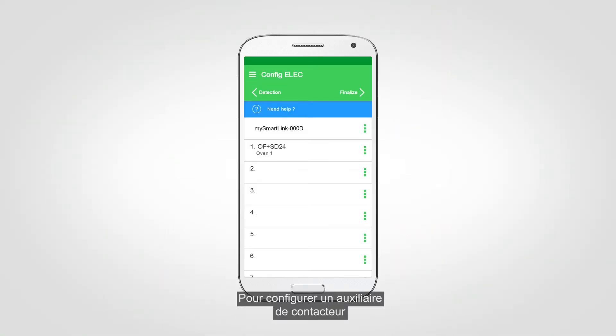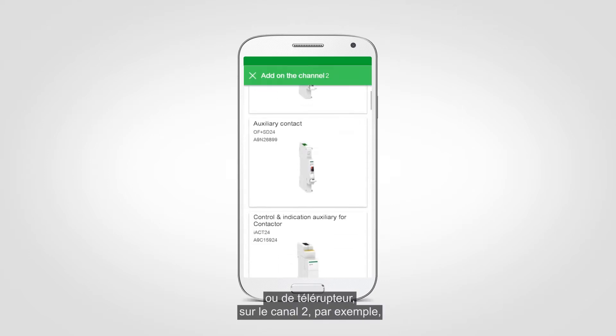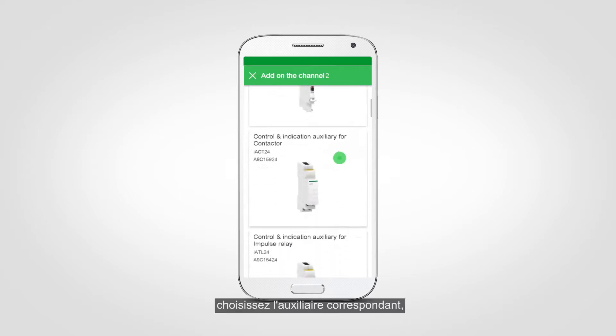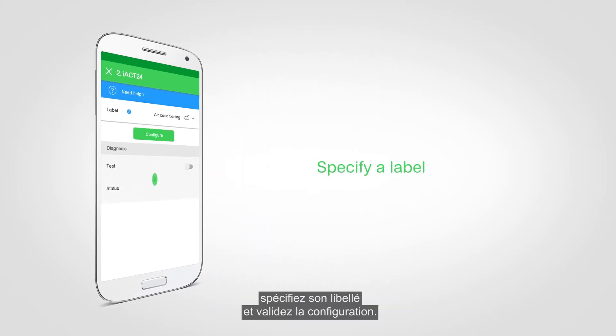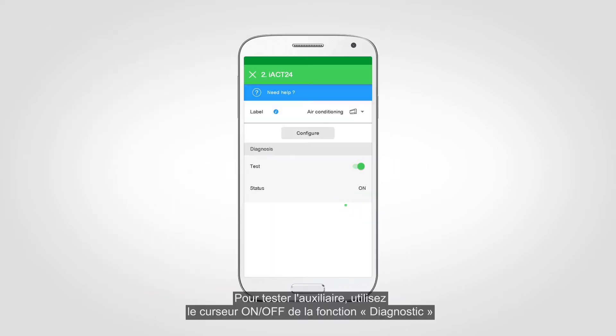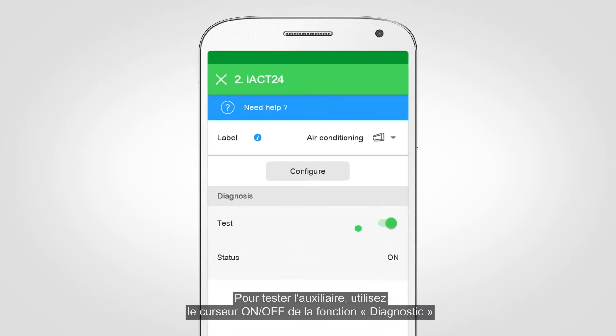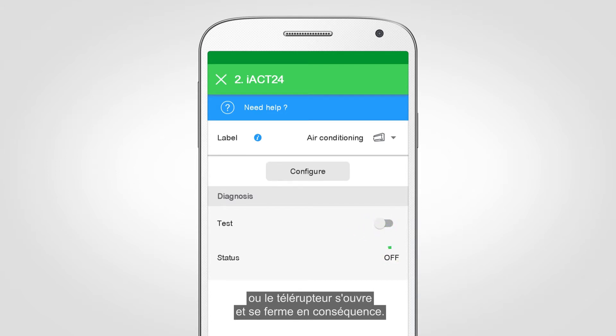To configure a control and indication auxiliary for contactor, or for impulse relay on channel 2, for example, select the corresponding auxiliary, specify its label, and validate the configuration. To test the auxiliary, use the on-off slider in the diagnosis section, and verify in the electrical panel that the contactor or impulse relay opens and closes accordingly.